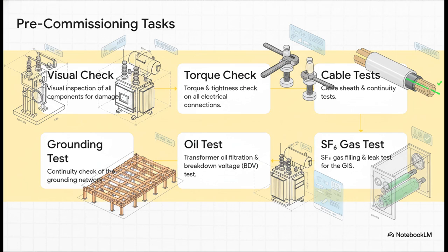Engineers are out there physically inspecting everything for damage. They're using torque wrenches on every connection because a single loose bolt can lead to a catastrophic failure. They test cable insulation, check for tiny leaks in the SF6 gas that prevents sparks, and purify the transformer oil. They even verify the entire station's safety ground grid. Nothing, and I mean nothing, is left to chance.